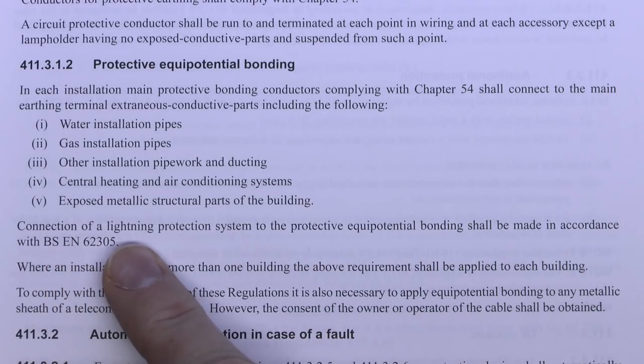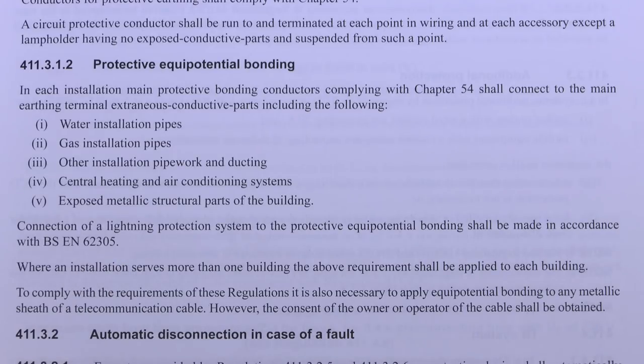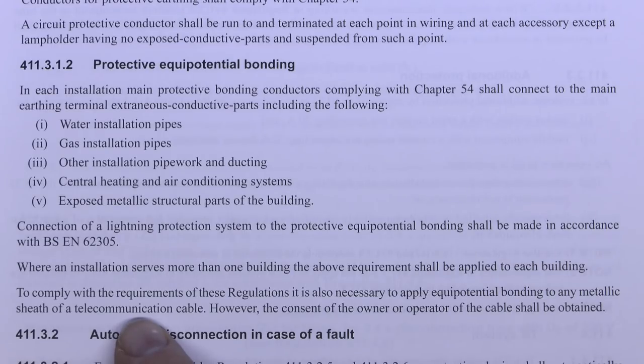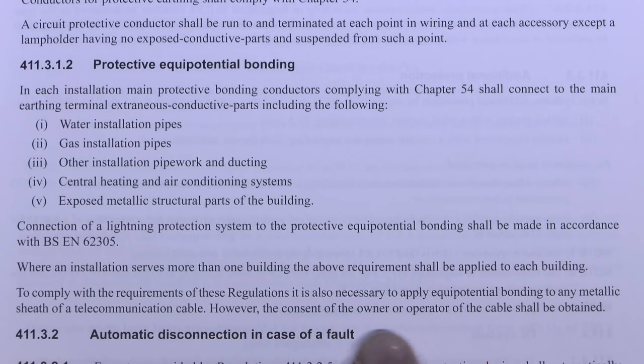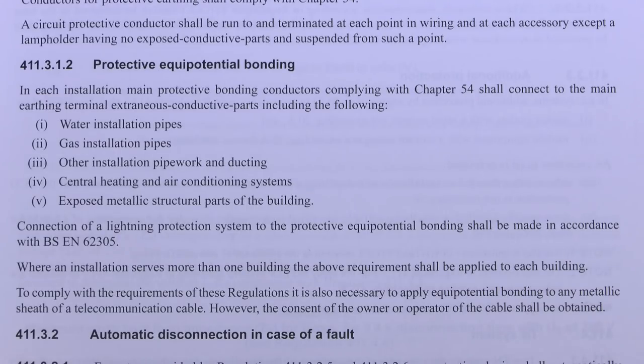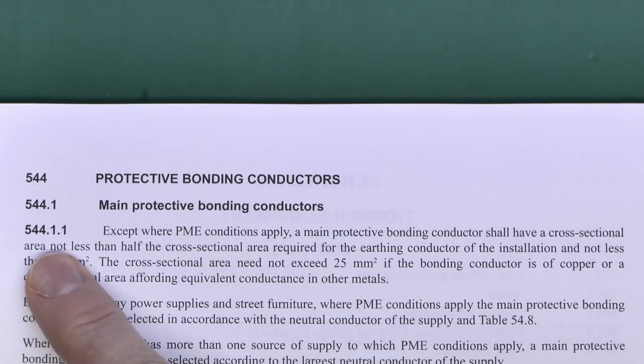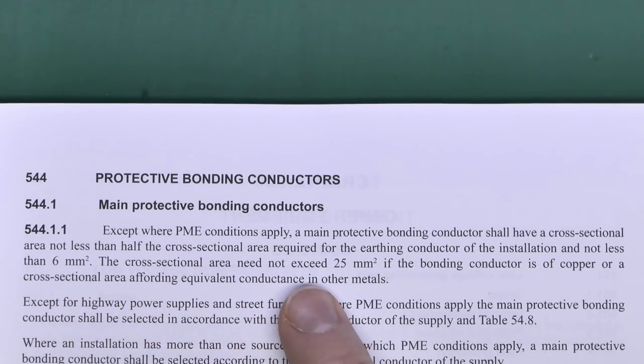There are a few notes: connection of a lightning protection system should be connected in accordance with the relevant standard, and when an installation serves more than one building these requirements should be applied to each building. There's also a note about the metallic sheath of a telecoms cable — typically an underground armoured cable — which should be connected, but the consent of the operator/owner of the cable should be obtained. The section dealing with the size of main protective bonding conductors is 544, part of chapter 54 which covers all protective conductors.